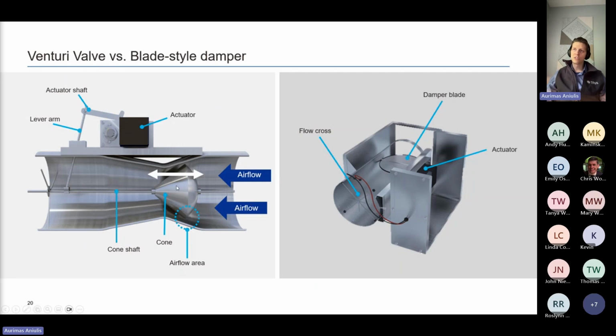So you can see that the airflow comes in, hits this cone, the air flows around the cone and exits on the other side. And what you get here is a mechanical pressure independent flow control. As your duct static pressure fluctuates on the inlet, that cone spring movement absorbs it and your output remains constant. On a VAV or blade style valve, you typically have some sort of a flow cross sensor, which is doing a delta P reading, which is converted into a CFM. That CFM is compared to a set point, and if it's below or above, an actuator is commanded to modulate the damper. So there's a continuous PID loop going in there, calculating CFM and adjusting the actuator in real time.